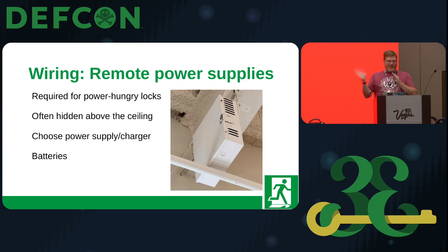And again, a little bit about those remote power supplies. They're required for power-hungry locks. Magnetic door locks are the worst for this because if you get too much of a voltage drop, then somebody can just pull on the door really hard and it'll open, but it looks like it's locked. And what'll happen is sometimes they'll run wire and they'll realize, oh, this is too far. We're just going to put a remote power supply up in the ceiling somewhere above a conference room, maybe above the door, not necessarily tell you that it's there. And then when the power goes out and that one door doesn't work, you have to figure out why it is. And they'll use the cheapest enclosure, the cheapest power supply. They won't put batteries on it. It won't have a tamper switch.